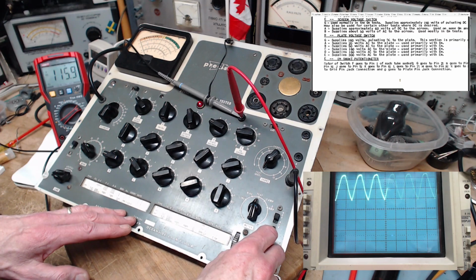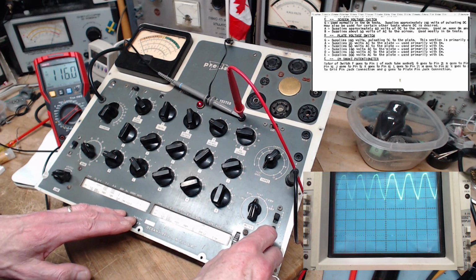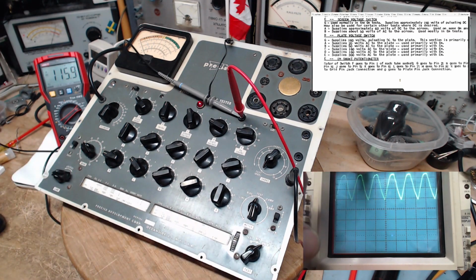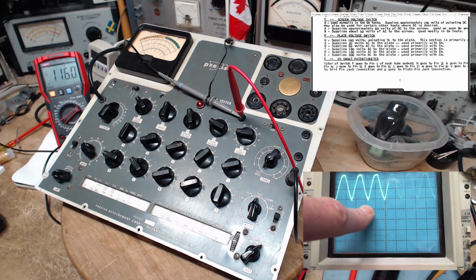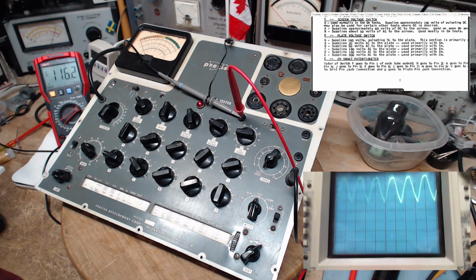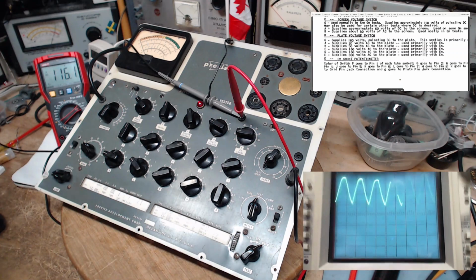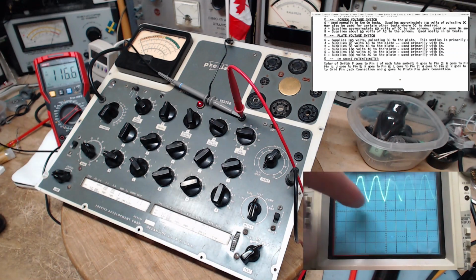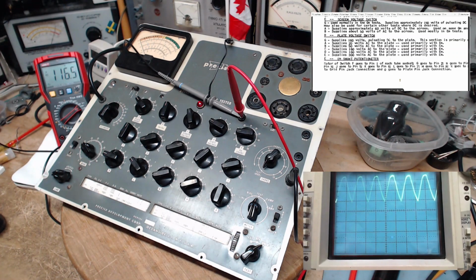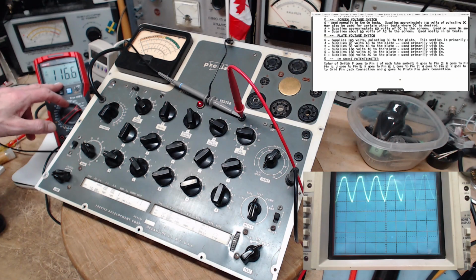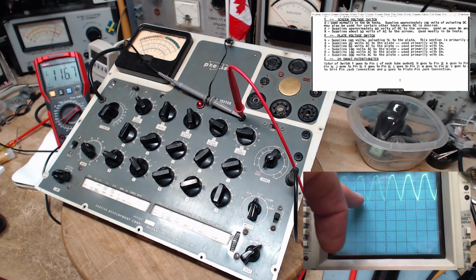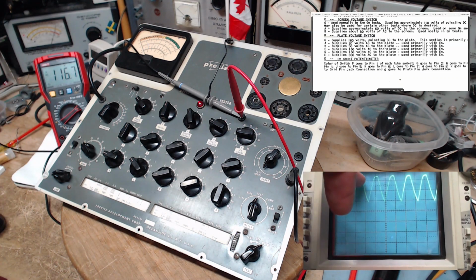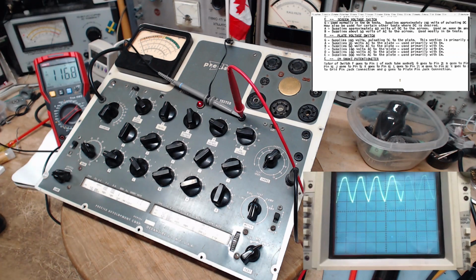So on the scope, that says to me that's perfect because this is a pulsating DC — it's not coming down to 0. But let me just check, make sure. That's the 0, so see, it's definitely above. And I'm going at 5 times 10, 50 — it's 50 volts elevated. But on the voltmeter I'm seeing 116. The actual voltage here would be the peak voltage anyway — 50, 100, 150, 175 or something of that sort on the peak.